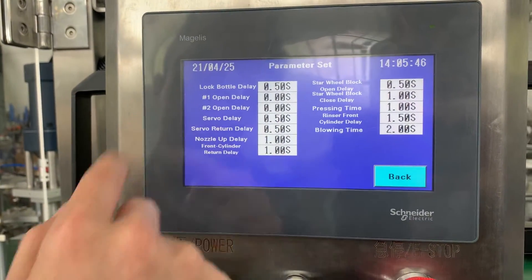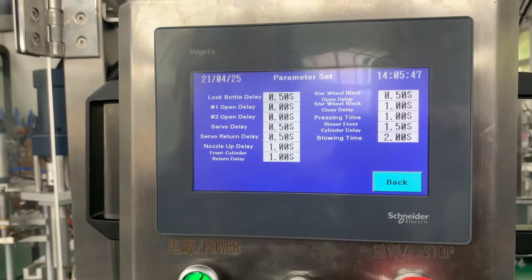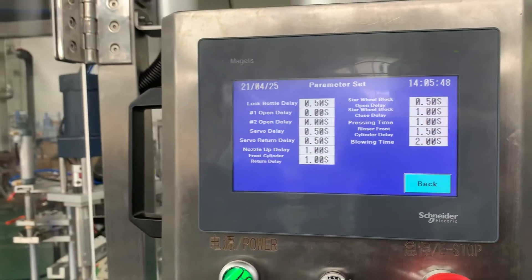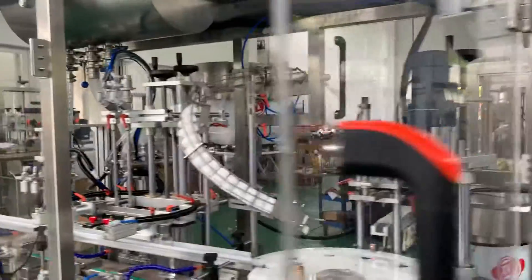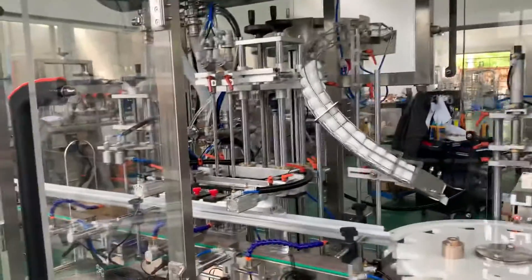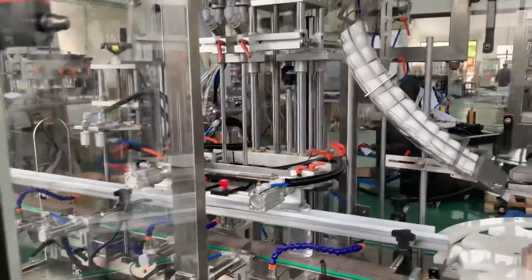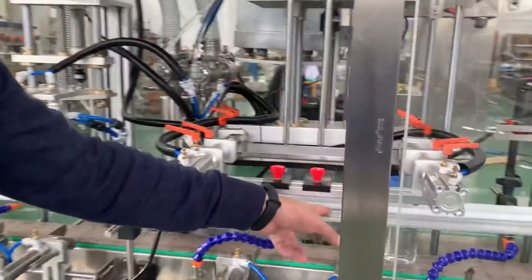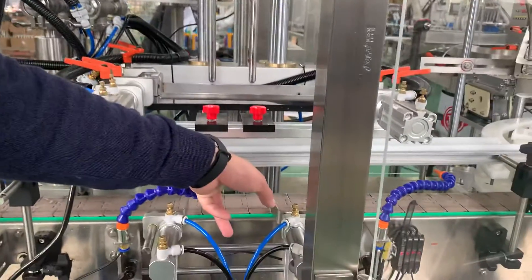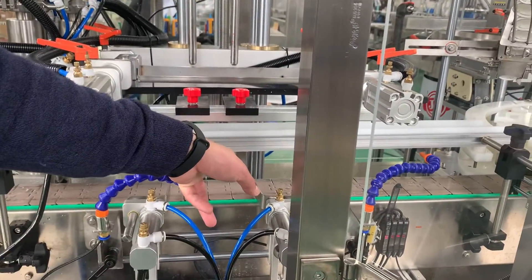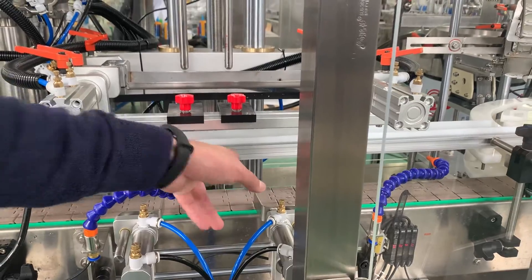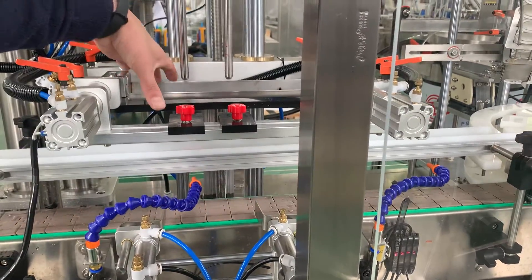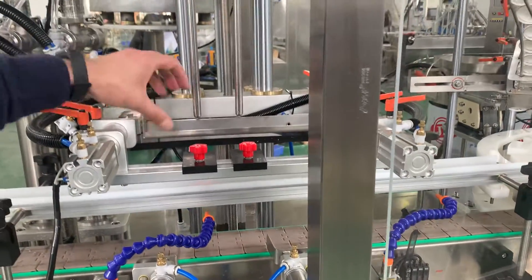The lock bottle delay means that when there are two bottles in position, the sensor detects them and after a delay this lock will activate. Normally this is set to 0.5 seconds and you do not need to change it.